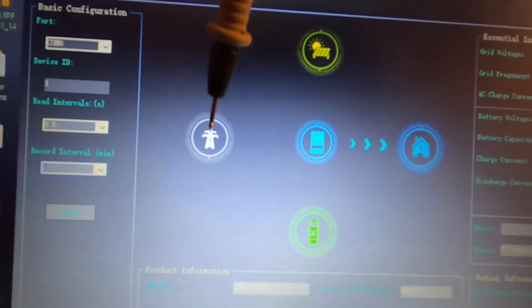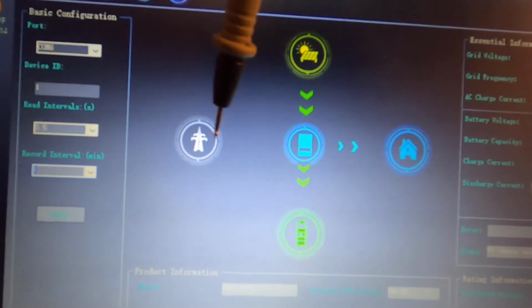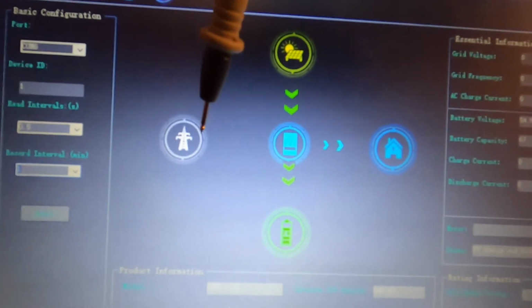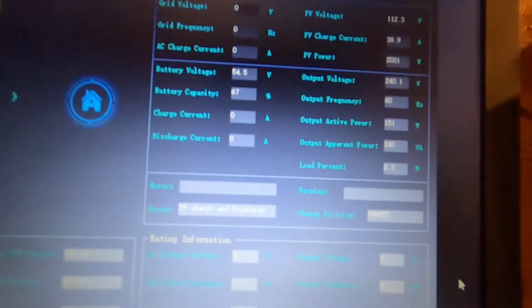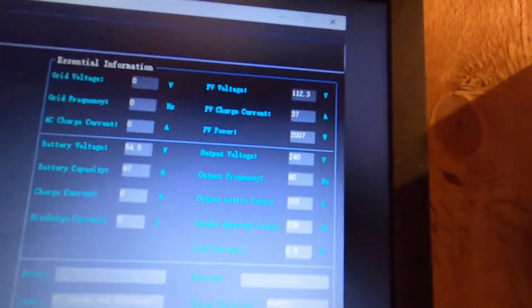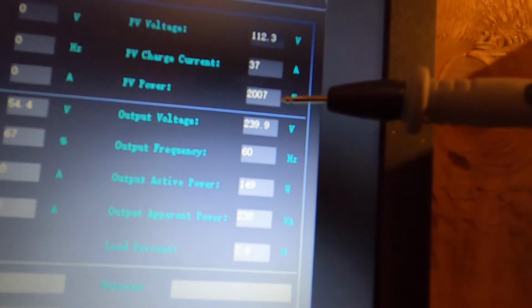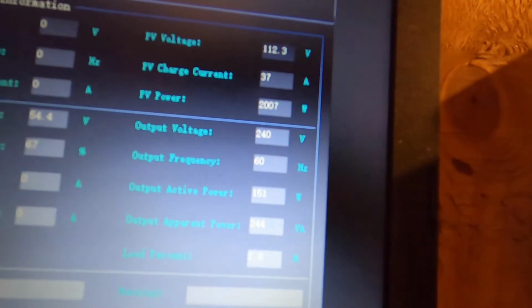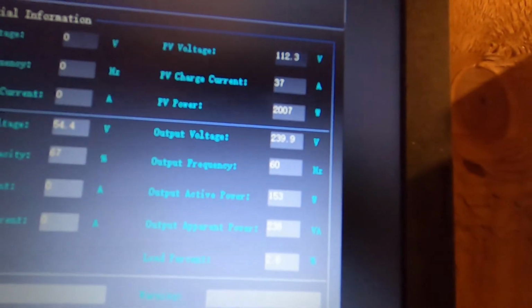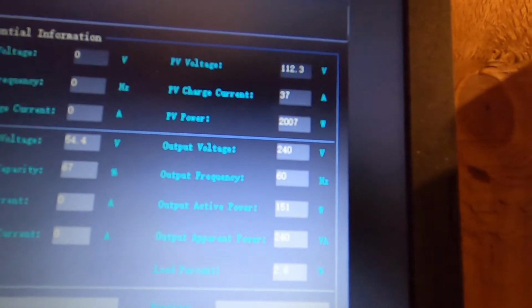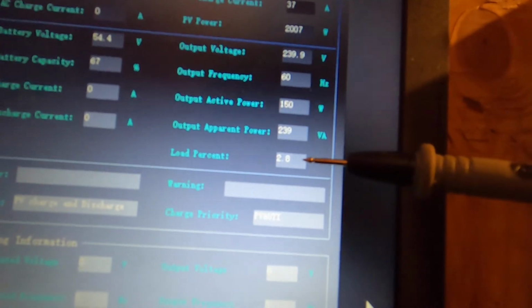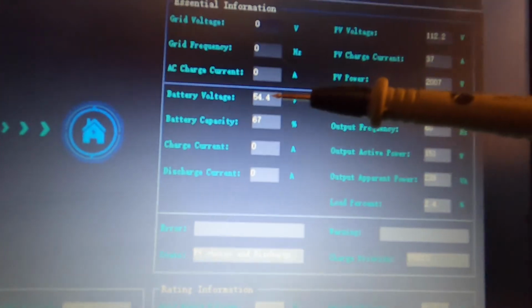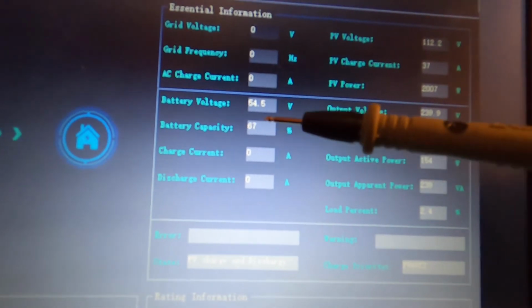This symbol here is the grid if we were tied in, but we're not. So you see there's nothing happening. It's not lit in any color. It's just off there, not hooked up. And then this is allowing us to monitor the input. So about 2 kilowatts, which is pretty decent. That's about half of what they can do maximum. But it is winter time and they're not at a perfect angle, so I'm happy with that amount. We're using about 150 watts of power right now, which is very little. 2.4% of our load capacity. And down on this side you see the batteries, 54.4, which is 67% full.